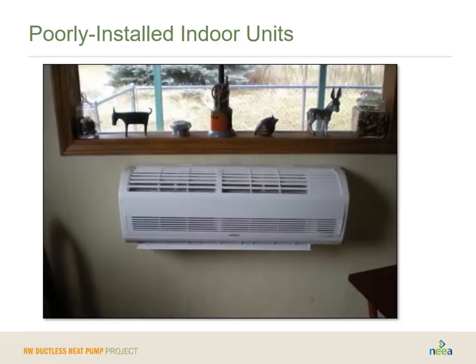Here we have a head that is neither high on the wall nor is it level. So this is really just not going to move the air as it's designed. If a homeowner doesn't have an option for a high on the wall head, they actually make what are called floor mounted units, which is a bit of a misnomer. It's actually mounted on the wall, but it's just at the level of the floor. And the difference is it pushes the air up into the room instead of down into the room. So it will work, and it will work very well, but we only really recommend those for this scenario where you can't put a head high on the wall. So this is a good example of probably the wrong piece of equipment was selected here, and it was not installed level.